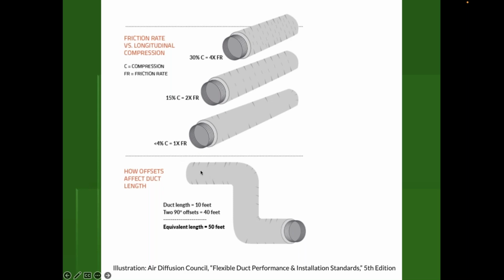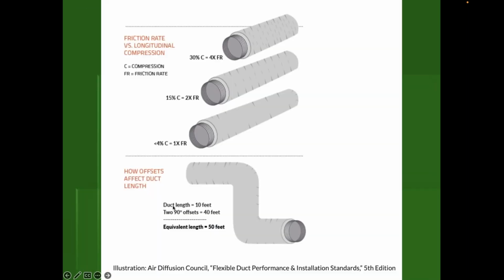Also keep in mind, flex duct can be really hard on your system and create much greater static pressure differences that make it harder for the system to push air throughout your house. For example, if we look at a bend like this, this duct length is actually 10 feet, but because of the 90s, it gives you an equivalent length of 50 feet. So it's really important to recognize the number of bends, and that we should have long sweeping bends. Use elbows here instead of the flex duct. It makes for a much more efficient system.